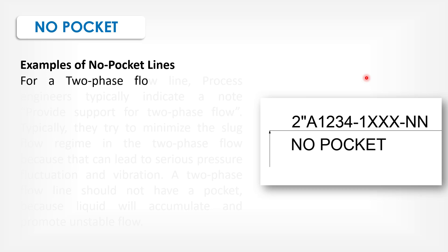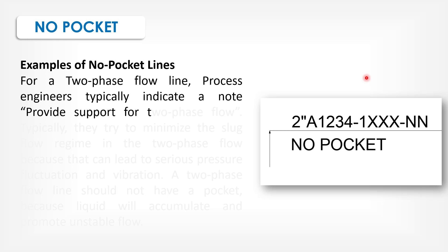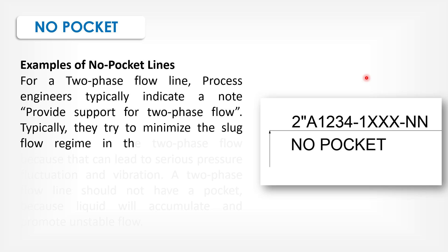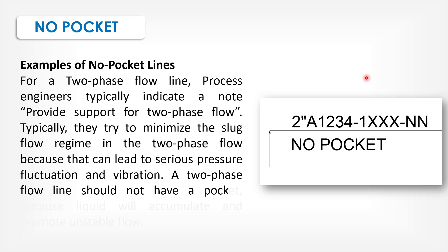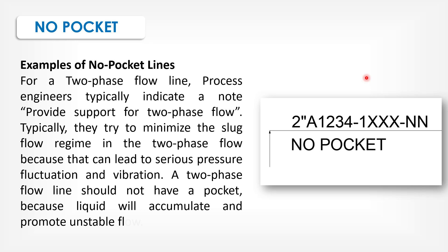For a two-phase flow line, process engineers typically indicate a note, "provide support for two-phase flow". Typically, they try to minimize the slug flow in two-phase flow because that can lead to serious pressure fluctuation and vibration. A two-phase flow line should not have a pocket because liquid will accumulate and promote unstable flow.